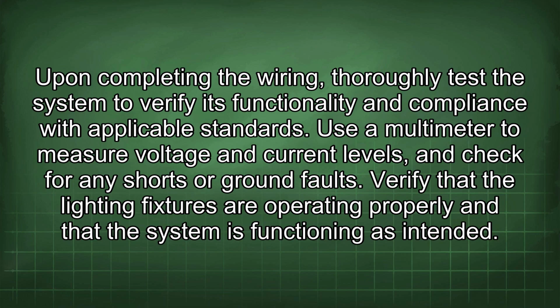Upon completing the wiring, thoroughly test the system to verify its functionality and compliance with applicable standards. Use a multimeter to measure voltage and current levels and check for any shorts or ground faults. Verify that the lighting fixtures are operating properly and that the system is functioning as intended.